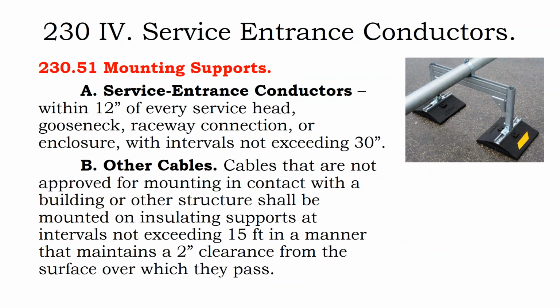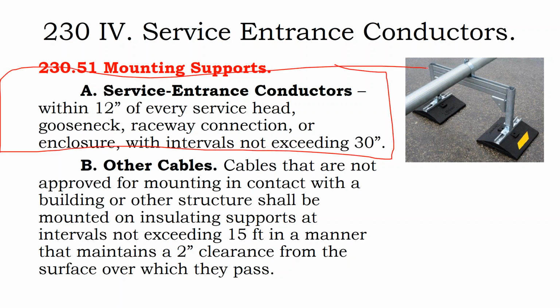There are support requirements for your service entrance conductor. Within 1 foot of every service head, gooseneck, raceway connection, with the intervals not to exceed 30 inches. And so for your solar array, here's a support requirement. You need to attach that gooseneck to the building within 12 inches for your above ground entrances. When your conduit is coming up from the ground, if it's a 3 foot tall conduit coming out of the ground, it needs 2 attachment points, or I guess that would be 42 inches. So at 3 feet, you might be able to get away with just 1 if you really want to.